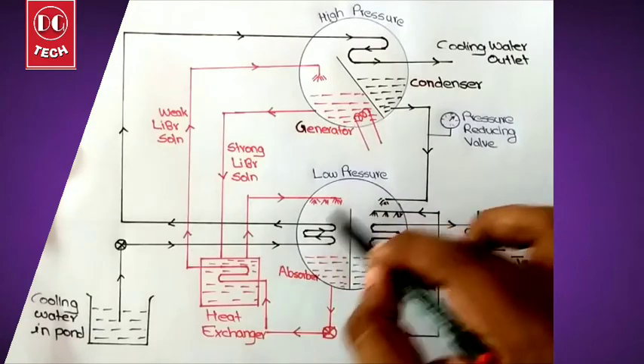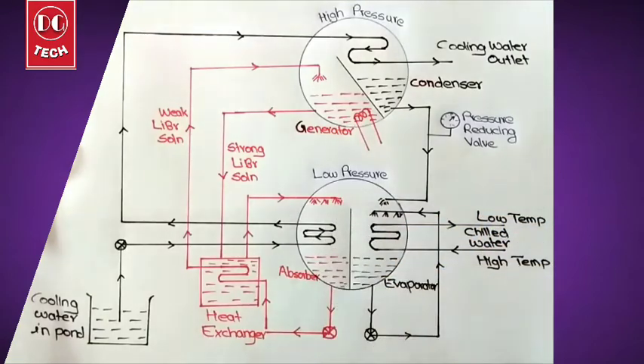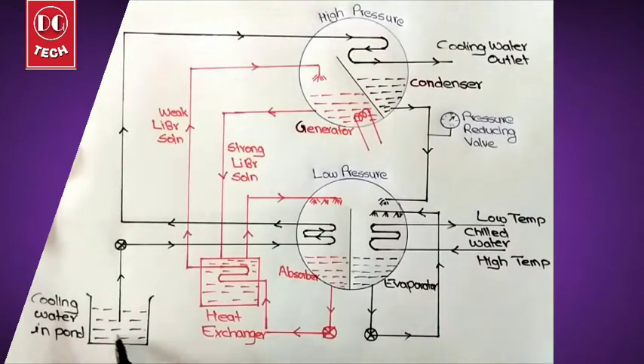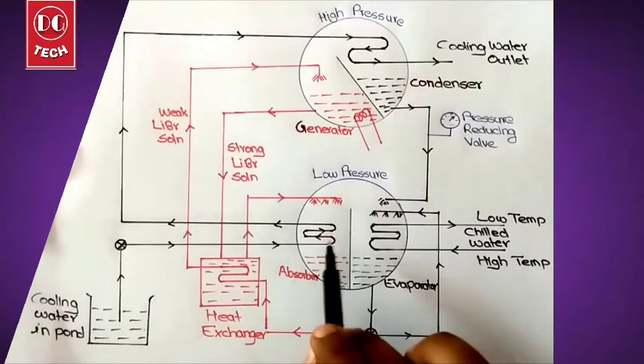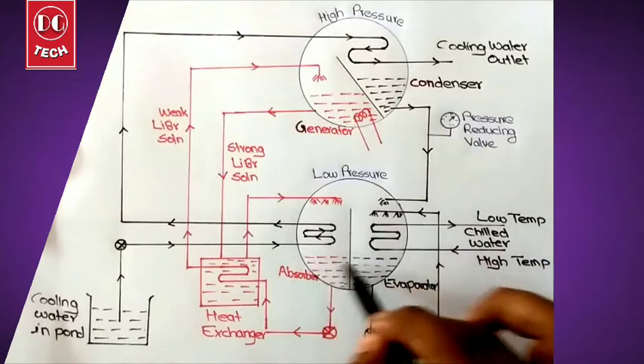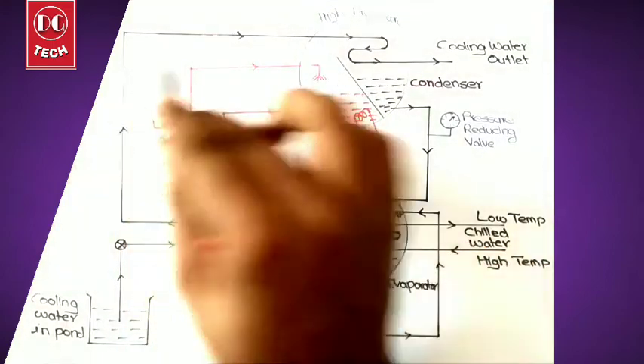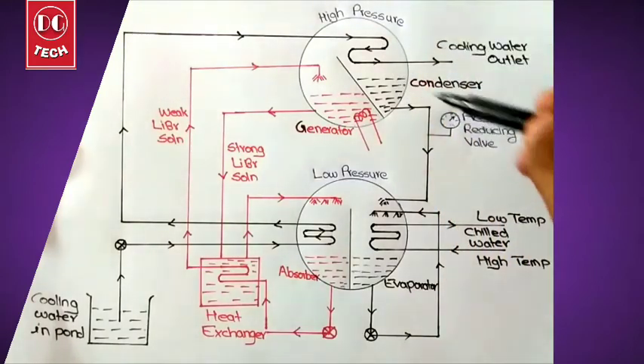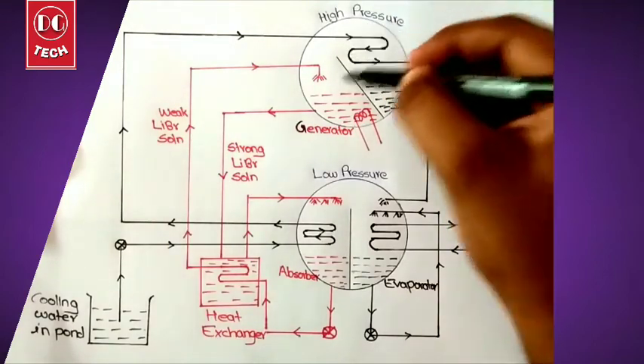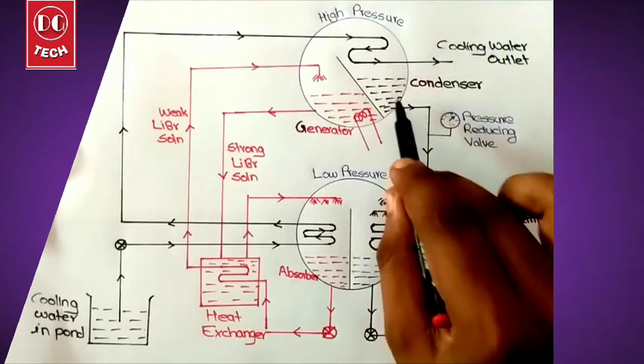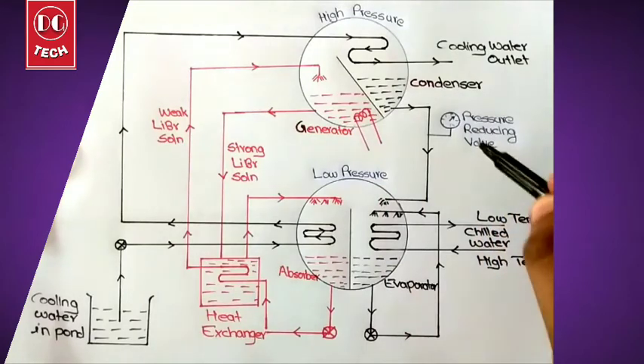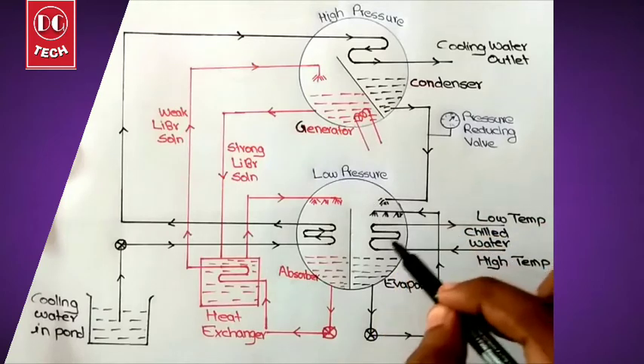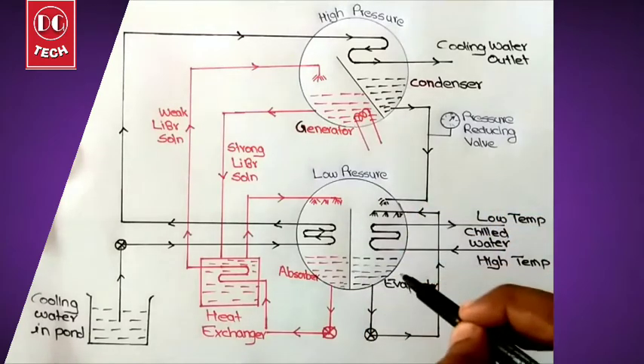The strong lithium bromide then passes through this pipe and gets sprinkled into the absorber. Cooling water from a pond is pumped to the absorber and condenser to reduce temperature. The water vapor from the generator gets condensed in the condenser, and the resulting water passes through a pressure-reducing valve to drop from high pressure to low pressure, reducing its temperature so we get cooled water, which is then passed through the evaporator.